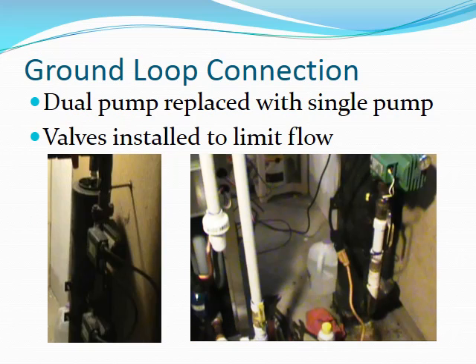The ground loop connection wasn't exactly easy, but it wasn't too difficult either. I had two pumps that were both at a 240 volt level, and I replaced them with a single 110 volt pump. The 110 volt pump was going to be wired into the system with a solenoid, and I'll get to that in a minute. But I also had to install some valves. Now the valves are pretty important here because they are needed to regulate to a temperature, so I had to be able to slow down the flow to achieve a certain temperature difference between the input and the output of the coil.